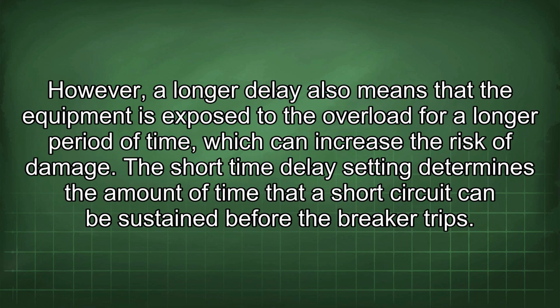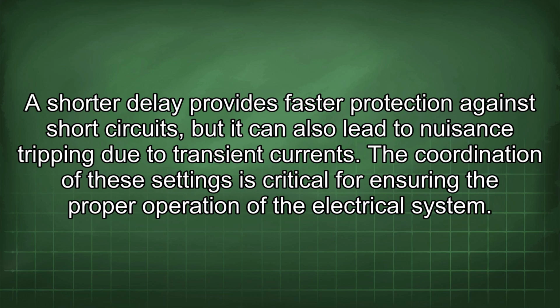However, a longer delay also means that the equipment is exposed to the overload for a longer period of time, which can increase the risk of damage. The short time delay setting determines the amount of time that a short circuit can be sustained before the breaker trips. A shorter delay provides faster protection against short circuits, but it can also lead to nuisance tripping due to transient currents. The coordination of these settings is critical for ensuring the proper operation of the electrical system.